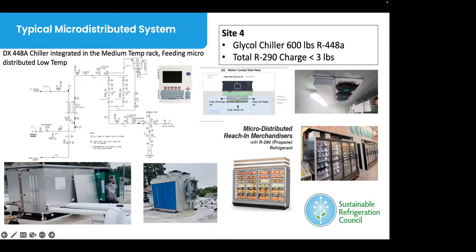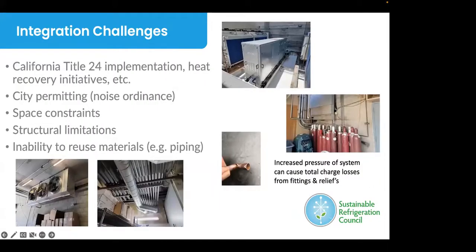The chiller, a Zero Zone chiller, produced chilled water that was provided to each one of those units out there, and that lower chilled water temperature increases the efficiency of the distributed systems. It ended up being the total charge in the system was less than 3 pounds of R290 and approximately 600 pounds of R-448A on the chiller.